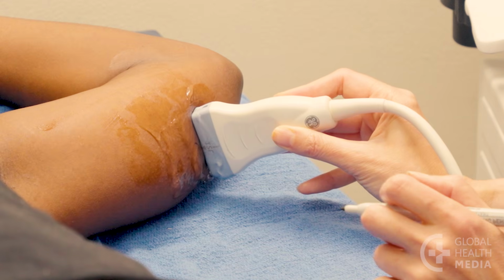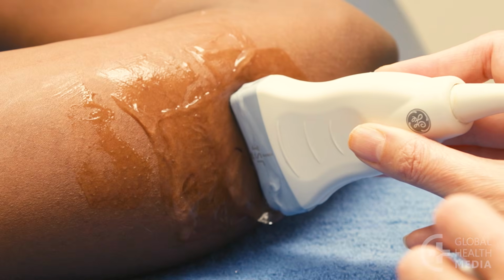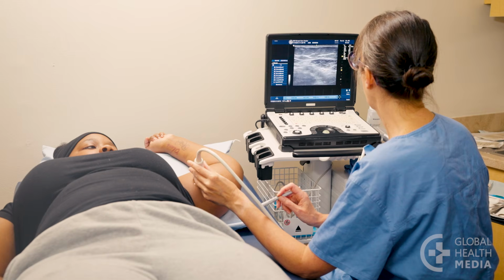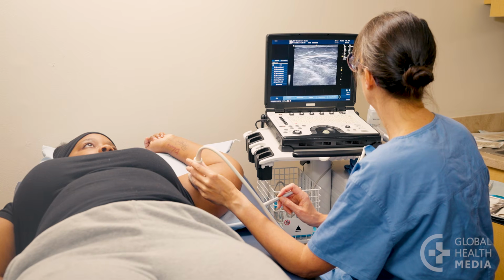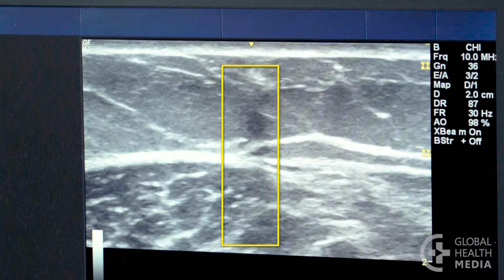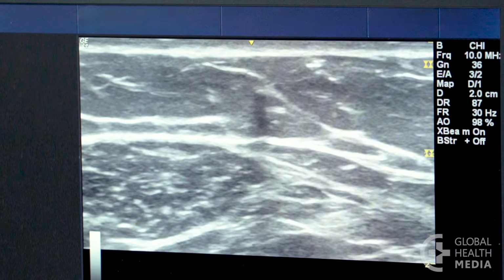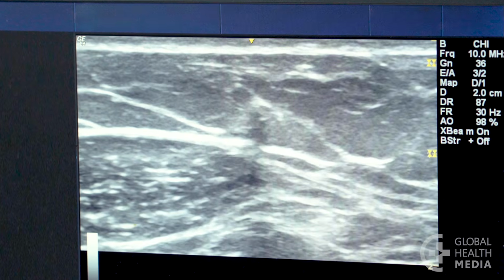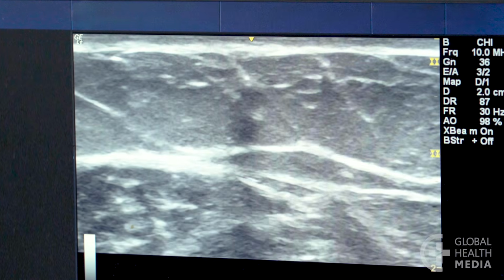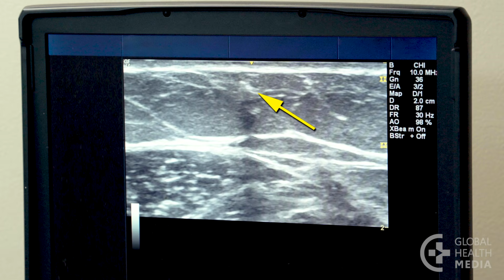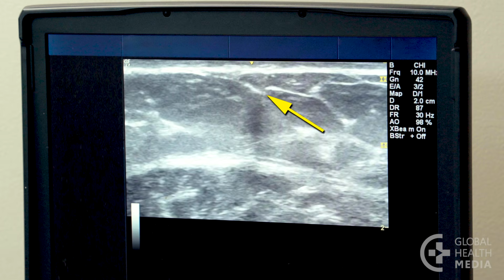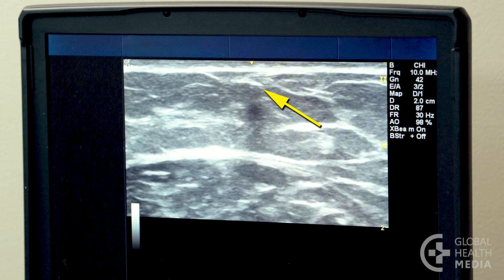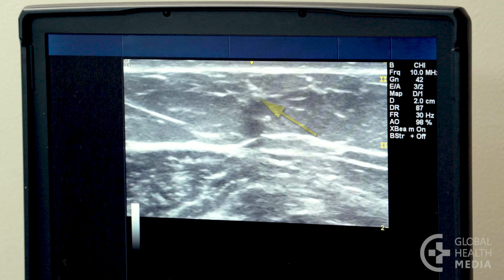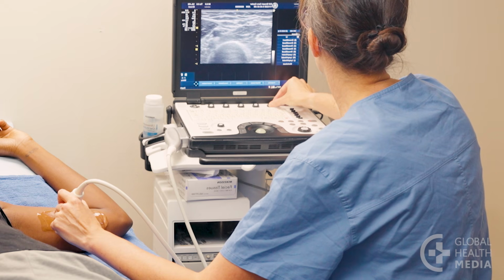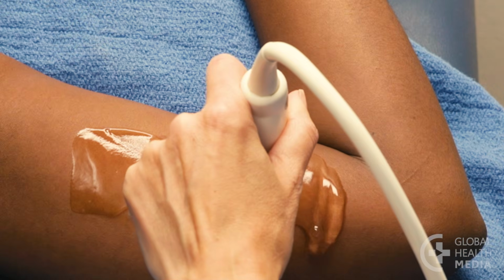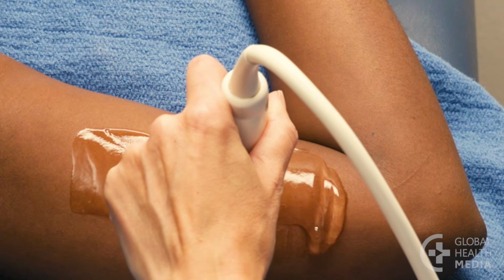To accurately identify the implant, hold the probe perpendicular and look for a dark linear shape. The dark line is the acoustic shadow of the rod as it blocks the sound waves of the ultrasound. Just above the dark linear shape is a white spot. This is the implant itself, located within the fat layer. If you don't see the dark linear shape, slowly broaden the area you're scanning.